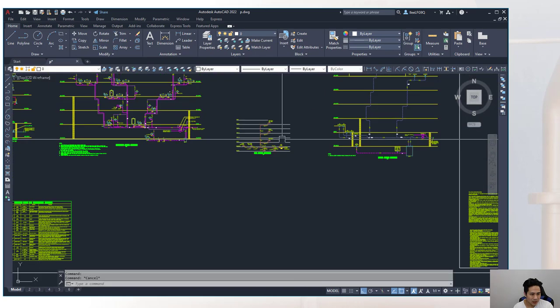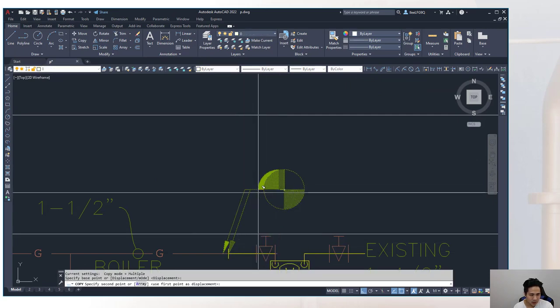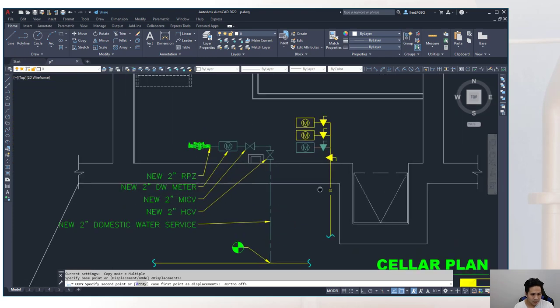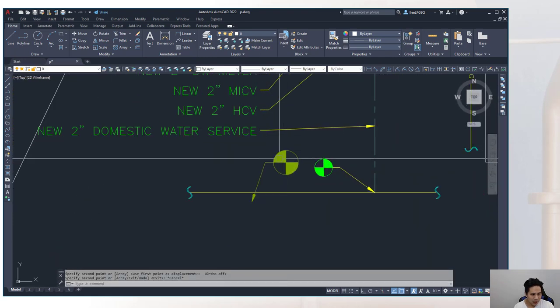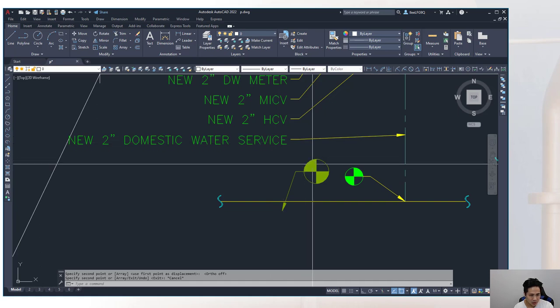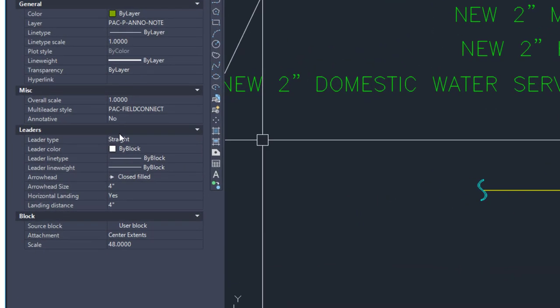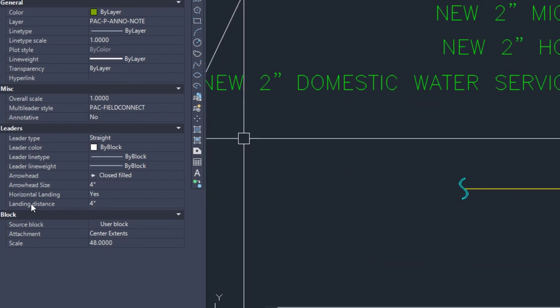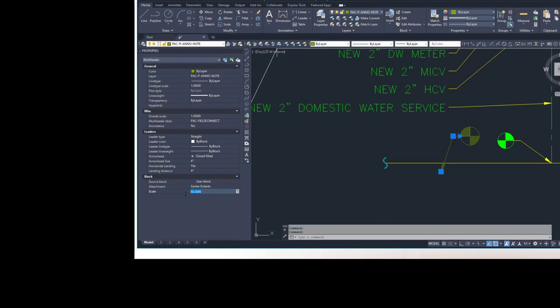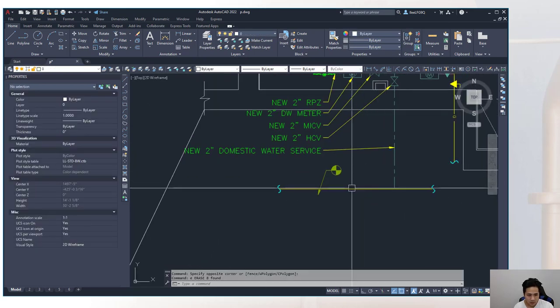Add a standard general plumbing note from the template stating that all piping shown is diagrammatic, minor offsets can be made to avoid field obstructions or for ease of installation by the plumber, piping to be run within wall and ceiling cavities where available, and that piping in exterior wall cavities should be kept as far from the exterior wall as practical with additional insulation to avoid freezing.